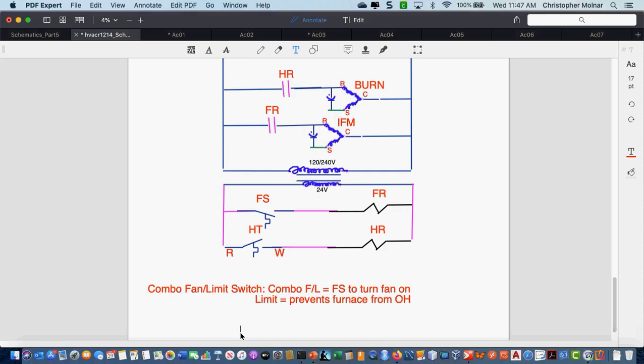Now, none of the other answers were wrong. Bad airflow can cause a furnace to overheat. Wrong ductwork size causes bad airflow. Yeah, a furnace will overheat. But your primary cause is basically a clogged filter, and then a valid repair is the blower motor has stopped working. Gets old, things burn out with age.